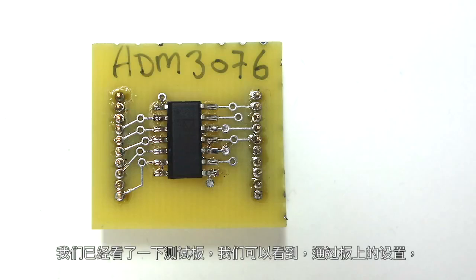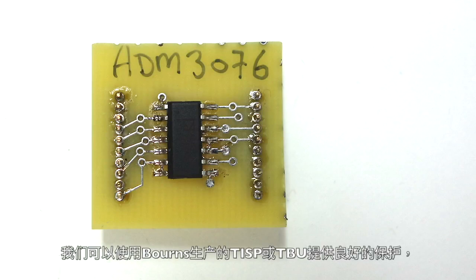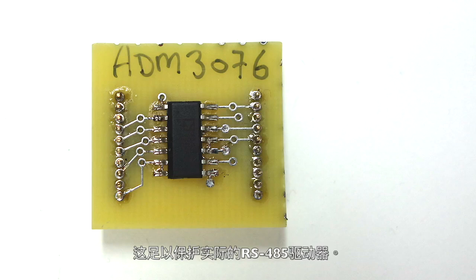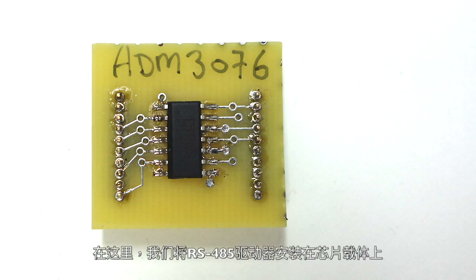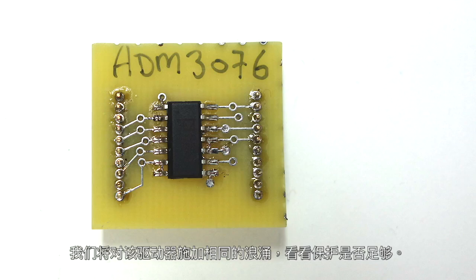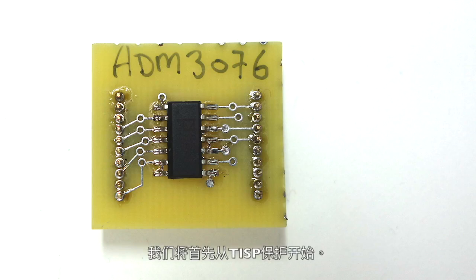We've taken a look at the evaluation board, and we can see that with the setup on the board we have good protection using TISP or TBU from Bourns. But is this protection sufficient for a real RS-485 driver? Here we've got an RS-485 driver mounted on a chip carrier, and we're going to apply the same surge to this device and see if the protection is adequate. We're going to start with the TISP protection first.